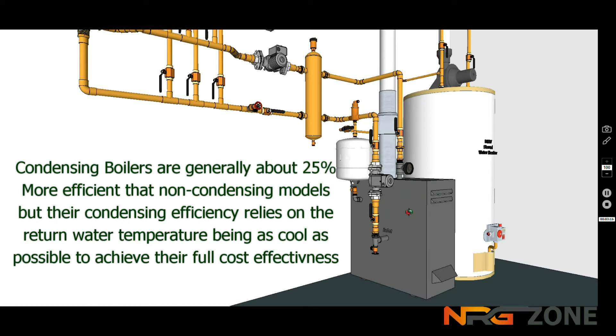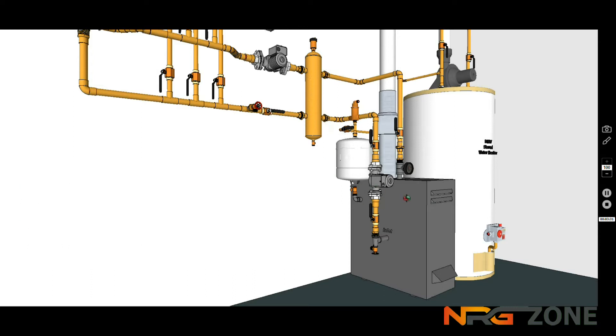Whereas with modern boilers, which are by far more efficient and cheaper to run, they rely on the coldest water going back. In this scenario with the low loss header, the return water is contaminated or mixed with the warm water from the boiler, so it can't get back to the boiler to cause condensation.